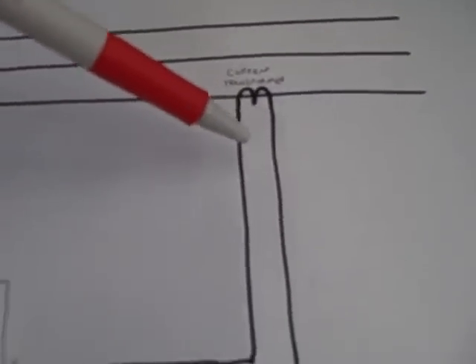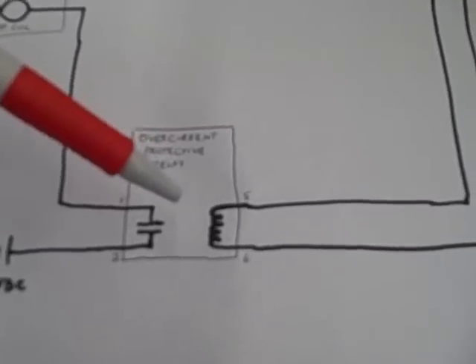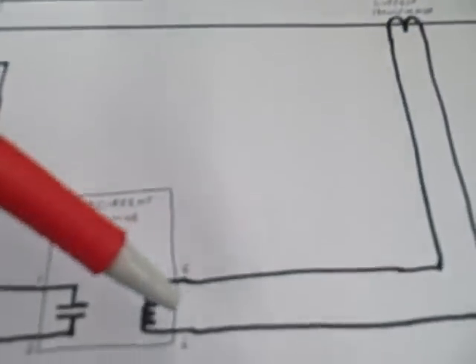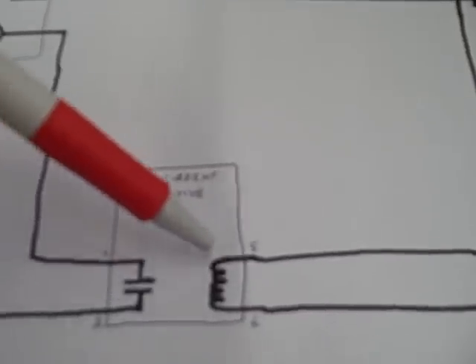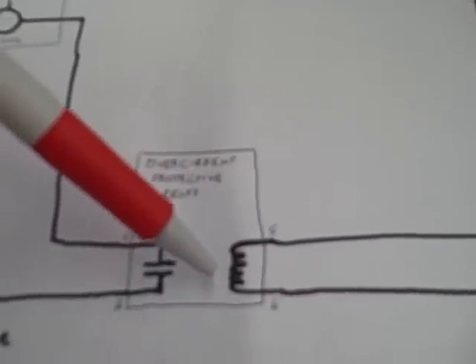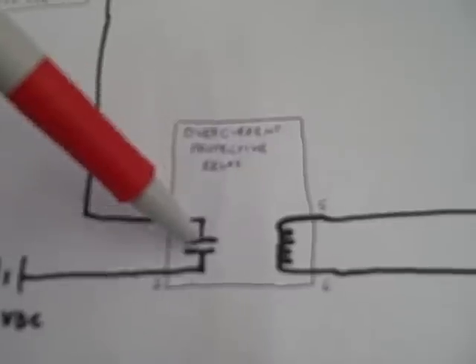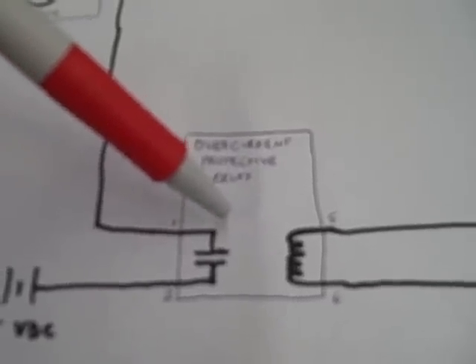This step-down lower current comes over to our protective relay, where in this case, with the old-style GE relay, that lower current is going to be driving an electromagnet coil. And that electromagnet coil moves the mechanism inside, and it's going to close this contact if the current becomes excessive.